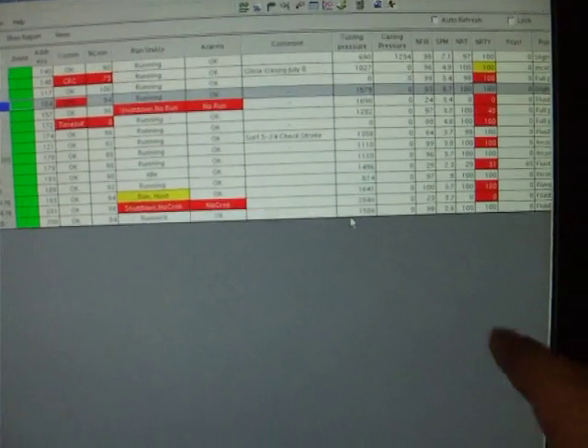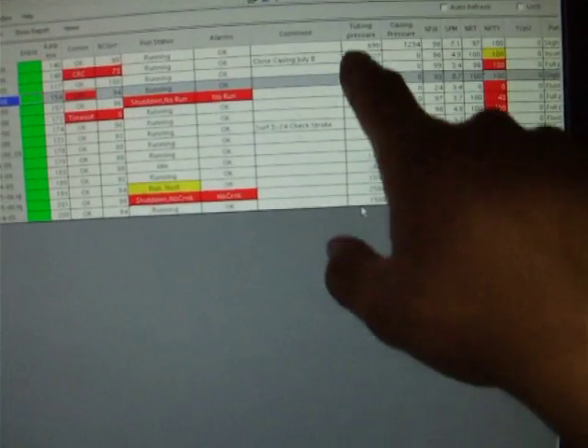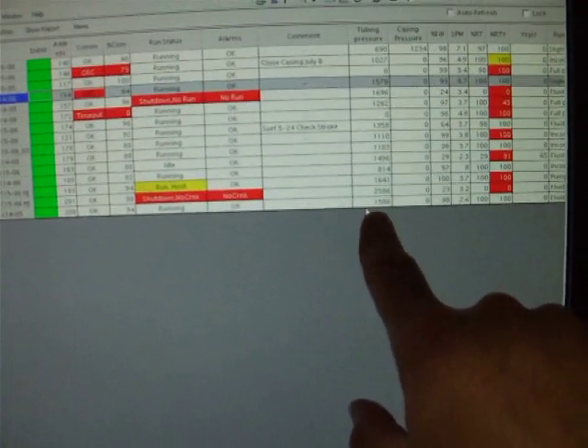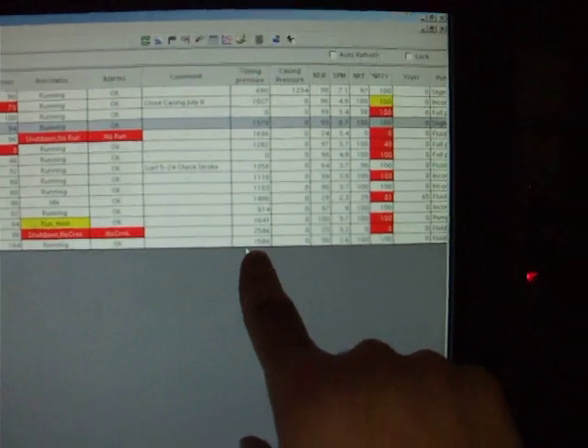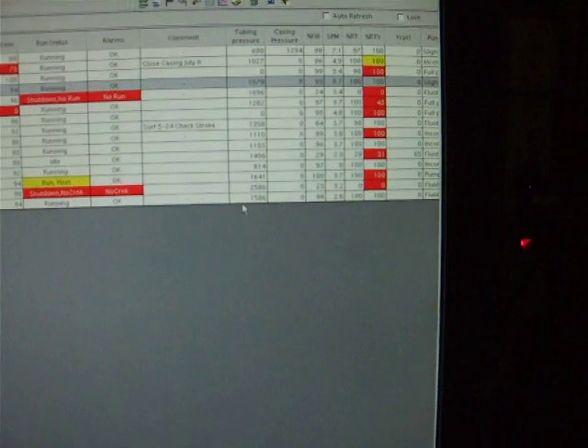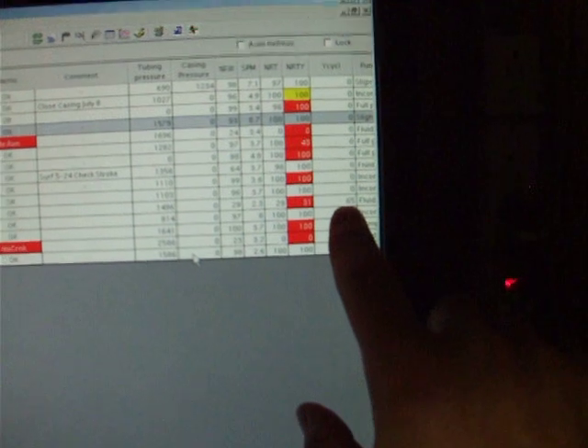It tells me tubing pressures via pressure transmitters, pump fillage, strokes per minute, today's run time, yesterday's run time, whatever I want. This well is actually running on and off in pump off control mode. It made 65 cycles yesterday.